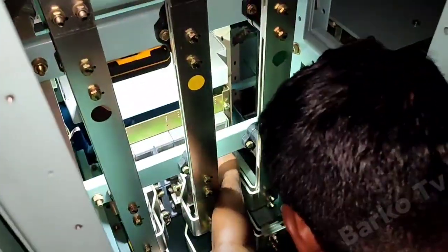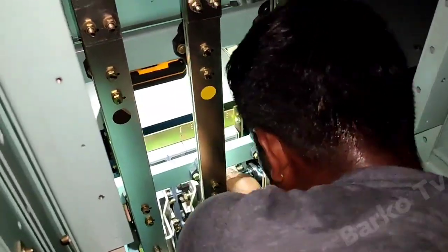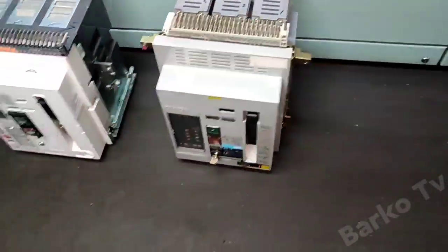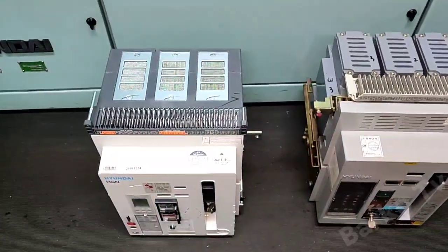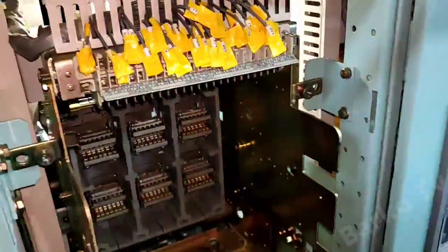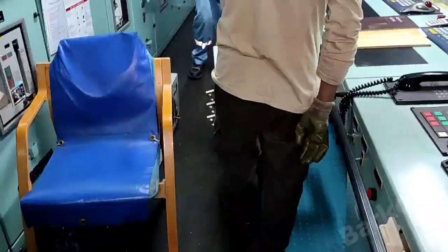They already removed the frame, including the existing bus bar connected to ACB number three. We need to retrofit this frame for the new ACB. This is the Hyundai HGN16 — that is the new type model of our breaker.